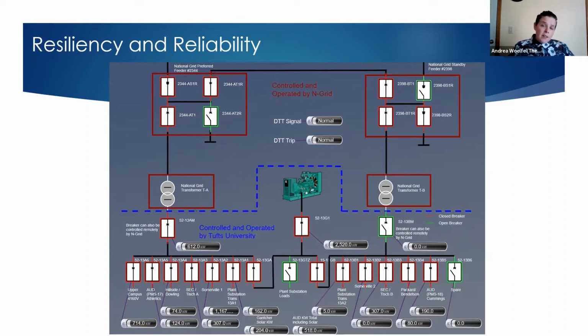We have the ability to go island as well. With this automated scheme, it's a protection too. Within a fraction of a second, we can protect ourselves from anything on the grid that we don't like, lightning strikes or whatnot. This resiliency and reliability, in combination with local building level emergency generation and UPS, gives the campus its most robust access to continual power. We also have the ability, as a microgrid, to go island, so the system can automatically shed buildings that are lower priority to keep everything we need running.